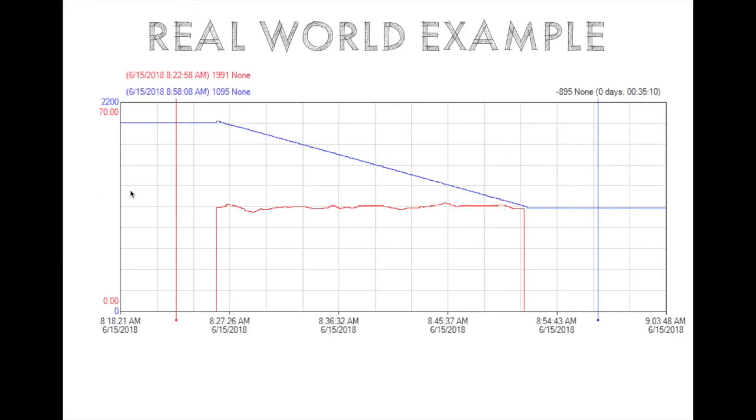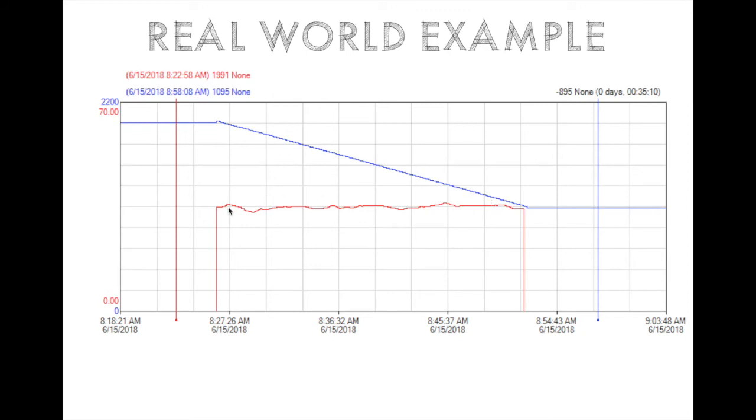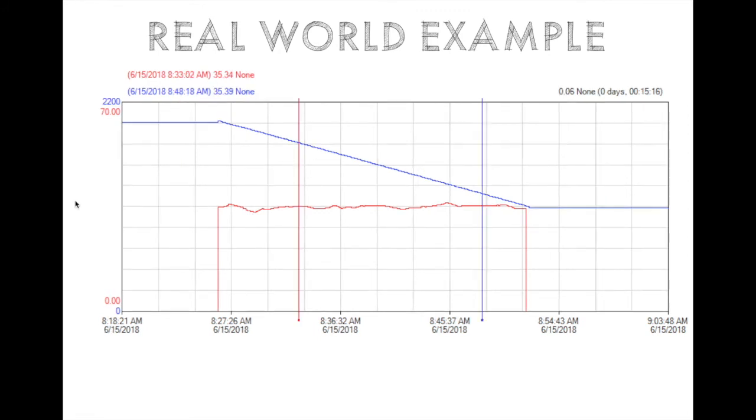So here's a real world example. In this plot, I have the surge tank. I'll just start calling it the hopper. The hopper weight, which is the blue. And over the course of this batch that we're making, the weight in the hopper is decreasing. And there's no refill shown here. The red is the flow rate. So it's about 35 pounds per minute of a white free-flowing powder. It's a lot like baking soda. That is coming out, that is being injected into our process.